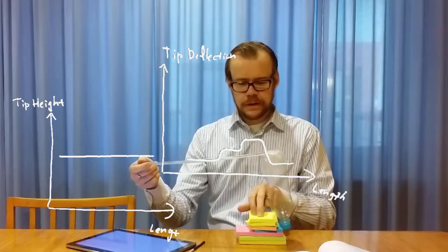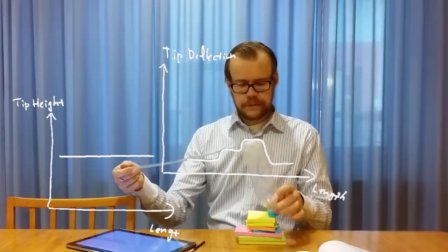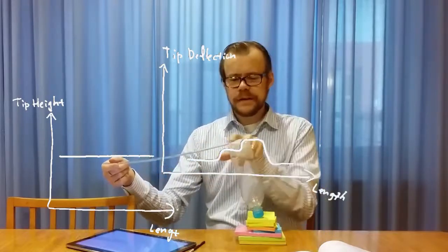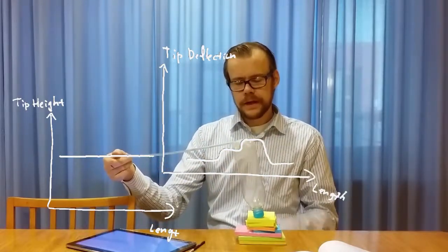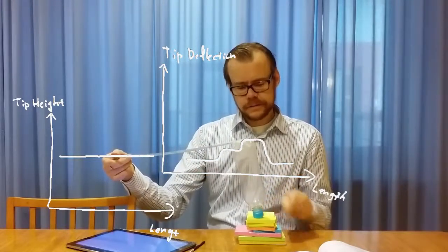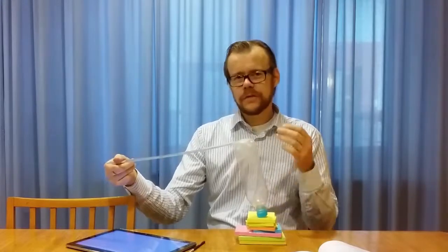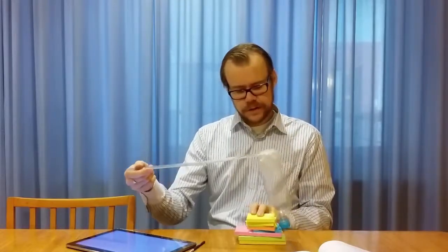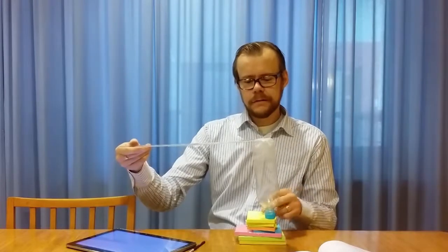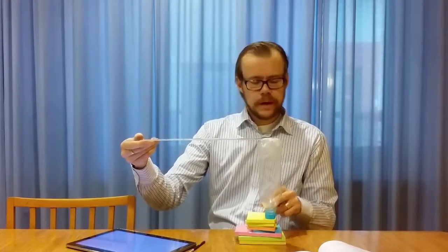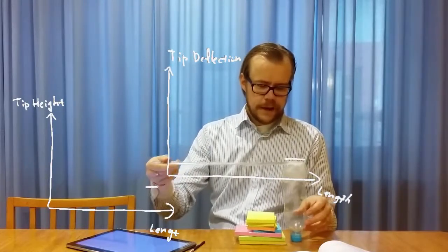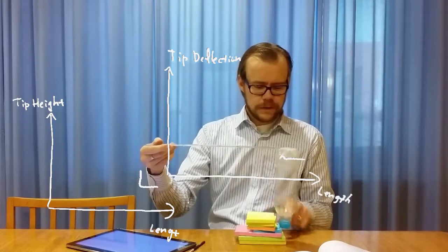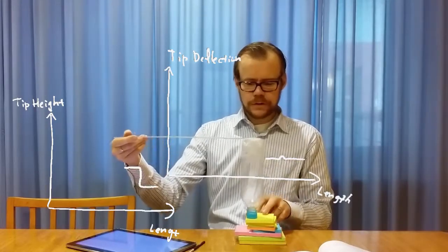When you scan the surface, this tip will deflect up like this when it goes over, and if you can measure this deflection of this cantilever, then you know the forces that are required when you go over the obstacles. And then you can use the same kind of control feedback loop as in the scanning tunneling microscope. So when I scan over this surface like this, the forces will be high when the tip goes up, and then I can use the control unit to regulate and compensate, so it loses the tension of the spring like this. And that means when I scan here, I can keep the tip as close as possible to the obstacles and follow the contours.